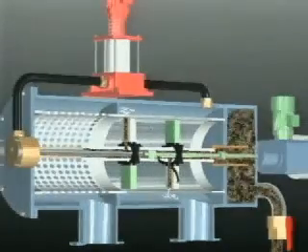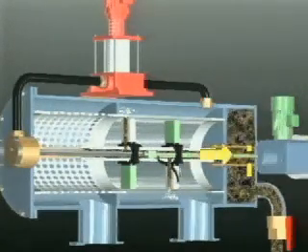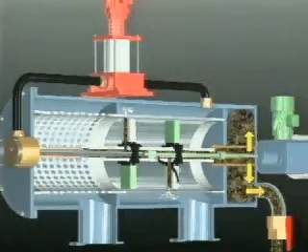The back flush stream passes through the screen into the collector nozzles, through the collector pipe, to the drain chamber, and flows out of the filter through a flush valve.